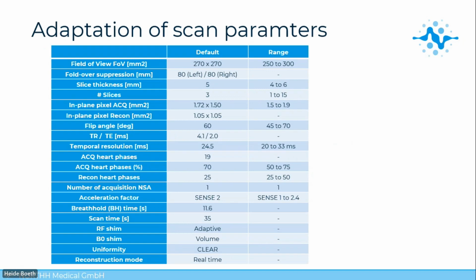If you go one slide further, these are the parameters we have found that work quite nicely. This is right now in Philips language, so I didn't translate all of these into the different vendor languages. You can see the field of view goes up to a range between 250 and 300, and there is fold-over suppression. We normally have a slice thickness of 5 millimeters and an in-plane acquisition of 1.7 to 1.5. I think the key is also the flip angle of 60 degrees. For Siemens, I think we had it at 70. We tried to have a quite fast temporal resolution of 24. In adults it is normally higher, 40 or 45 or something like this, so of course we need to be a little bit faster here. And we have a SENSE factor of 2.4.